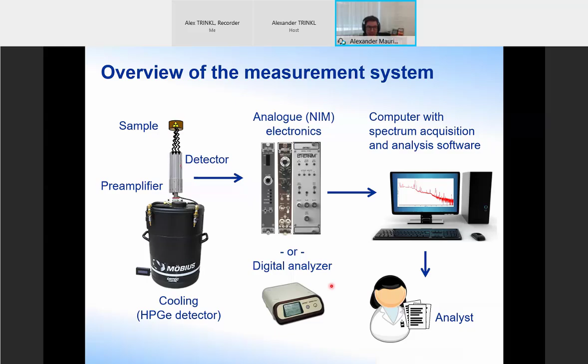So we'll go into a little bit of detail about each type now. We will divide the two main types of detectors used for gamma ray spectrometry. First, scintillation detectors, based on the scintillation principle. So it's a crystal which emits light when photon energy is absorbed in it. You'll see some typical configurations here, such as sodium iodide, lanthanum bromide, cerium bromide, cesium iodide, and so on. Then you have the semiconductor type detector, which has another detection principle, which we'll go into a little bit later. It has different possibilities, such as high purity germanium, silicon, and cadmium zinc telluride, I guess are the main ones.